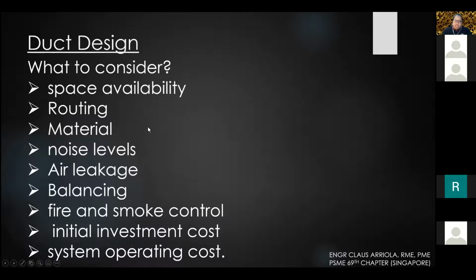Especially when you're designing a smoke engineering fan, these are very, very large ducts. The volume of air based on the space will create a large duct, which sometimes creates trouble from the architect's point of view, because how can he manage a very large duct that can be seen by all of the tenants and especially the client? Then he designs the architecture very systematically. If there's a large duct hanging in a large space on a corridor, that's very ugly, right?